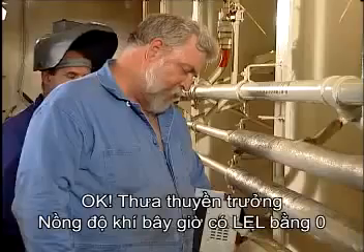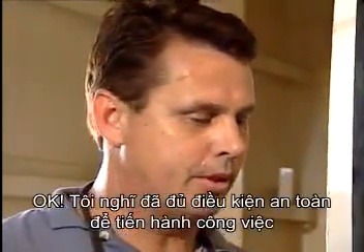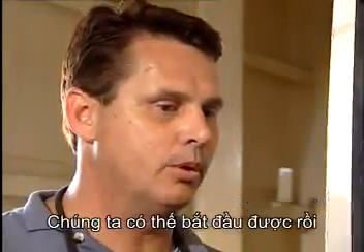Okay, Captain, the LEL is 0. The oxygen is 20.8. Okay, fellows, I guess it's safe to go ahead and start the hot work. Go ahead and get started.